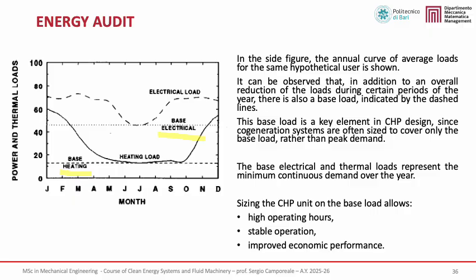In practice, cogeneration systems are often sized to cover the base load rather than peak demand in order to maximize operating hours. Sizing the CHP unit on the base load typically results in more stable operation, higher utilization of the system, and improved economic performance.